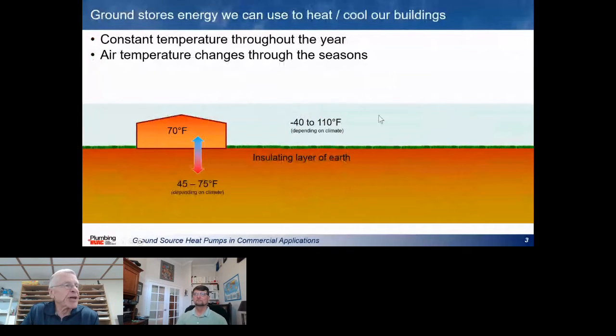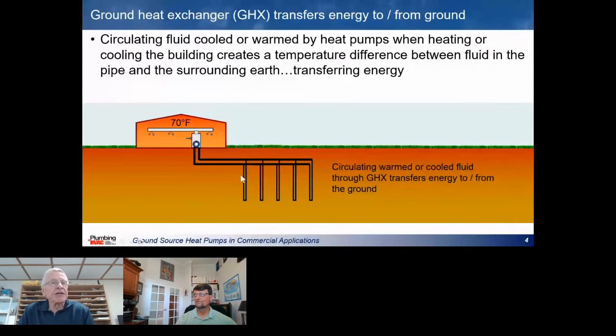So a quick primer of what a geothermal system is. Basically, what a ground source system does is exchange heat between the building and the earth below it. So the air temperature, as you know, in our climate especially, can range anywhere from -40 to about a plus 110 degrees Fahrenheit, or -40 C to about 40 or 45 degrees C. That reduces the efficiency of an air source heat pump pretty significantly if we start using the outside air as a heat source or a heat sink. The ground is a much more moderate temperature. In our climate, we're looking at anywhere from about 43, 44 degrees Fahrenheit up to probably about 55 degrees Fahrenheit across Canada. And that's a much more moderate heat source and heat sink than the air source.